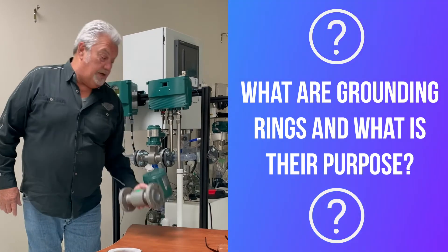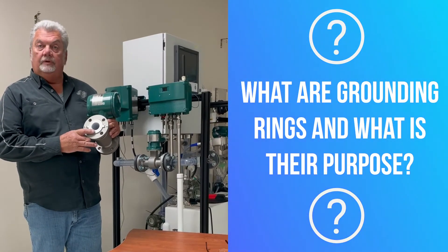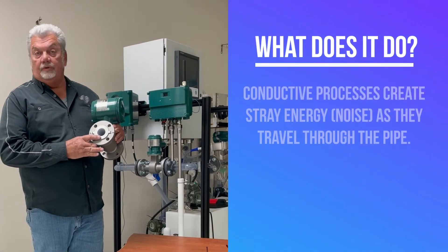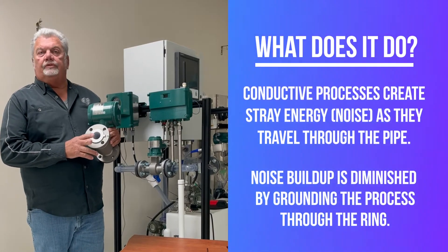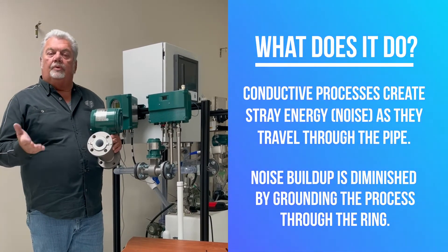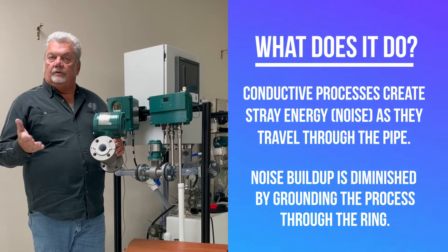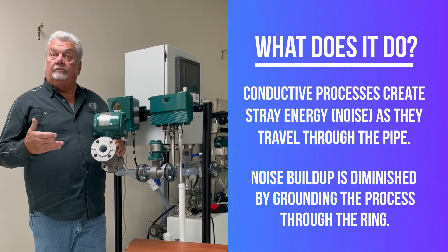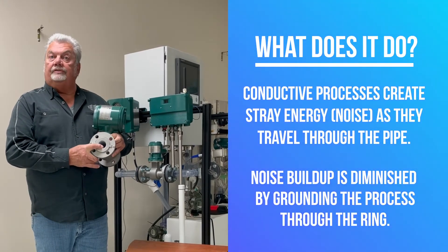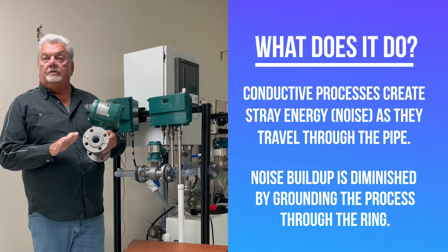I have an AXF here in my hand. As you can see, with Yokogawa, we pre-mount the earth ring or grounding ring. What this does is ground the process. With any mag meter, all processes are conductive. As they travel through the pipe, be it PVC or steel, it's going to create stray energy. What this is going to do is ground the process and knock down this noise. At Yokogawa, we always say all devices need to be properly grounded.